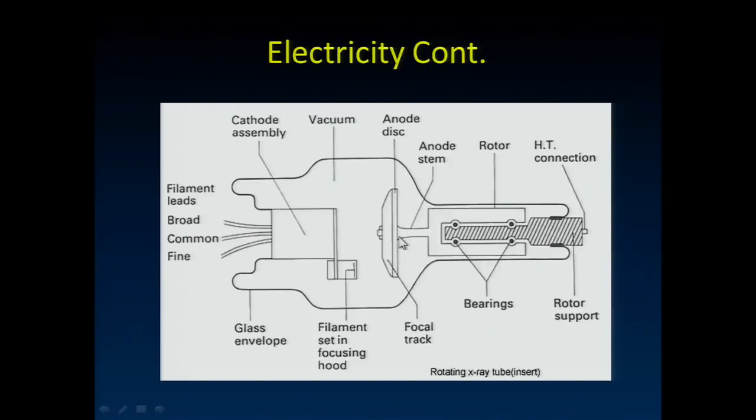And that's on the order of 100,000 volts. And that electron is now accelerated towards that anode and strikes it with a lot of energy. How much? Well, 100,000 electron volts, 100 keV when it strikes that. That's how much kinetic energy it has. That creates a lot of heat that ends up dissipated in this anode here.